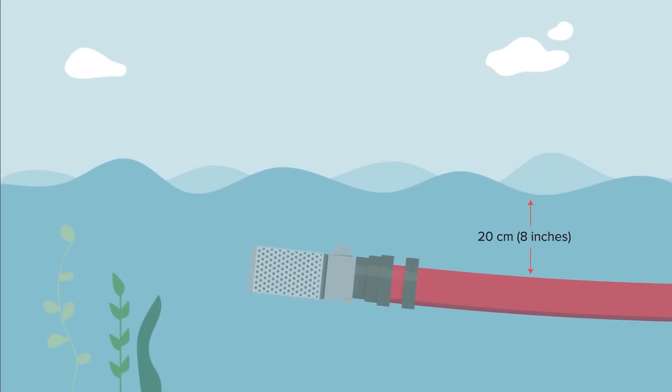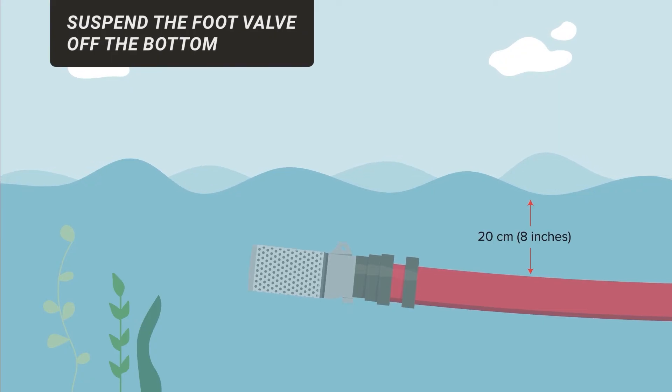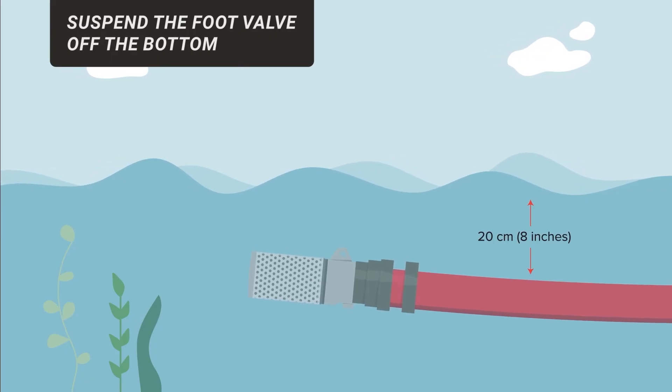Allowing at least 20 centimeters of water above the foot valve will stop any air from being sucked into the pump end. Suspend the foot valve off the bottom if sand, gravel, mud or other material could be drawn into the pump.